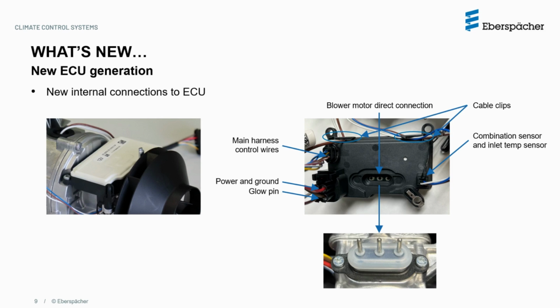Watch out when reassembling the ECU so it goes down straight into place by hand and not by using the 3 screws, otherwise you may risk breaking the 3 prongs on the blower motor assembly below. After snugging the ECU screws, always turn the blower wheel by hand to make sure no cable is touching it. Also take care when closing the top cover so no wire is crushed.